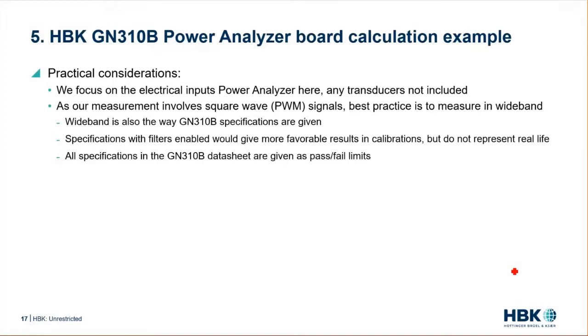Let's get to an actual calculation example based on the GN310B power analyzer. We need to take a few practical considerations. We focus on the electrical inputs for the power analyzer only here today and are not including any transducers, as our measurements involve square wave or modulated signals. Best practice is to measure in wideband, so without any filters applied.